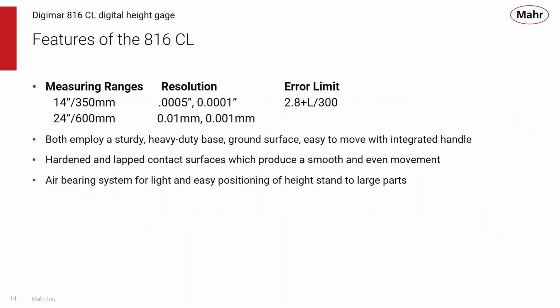Now, some of the other features of the 816 is the fact that it comes in two measuring sizes, a 14 or a 350 millimeter version, or a 24 and 600 millimeter version. They're both switchable from inch to metric with a 1/10 resolution or 1 micron resolution, and they both have the same error limit of 2.8 microns plus the length that you're measuring. So you have to remember that, you're really improving the measuring process if you're only measuring from over a short span. So that short span can be anywhere within its full measuring range, and you have the 2.8 micron accuracy.